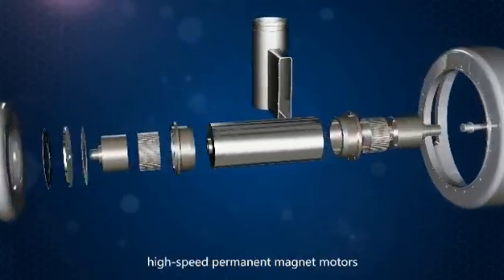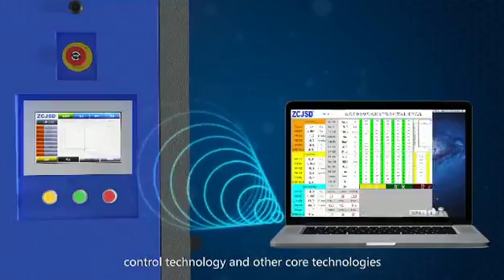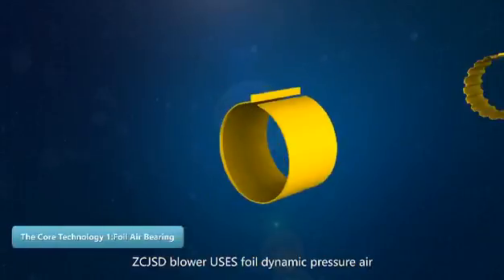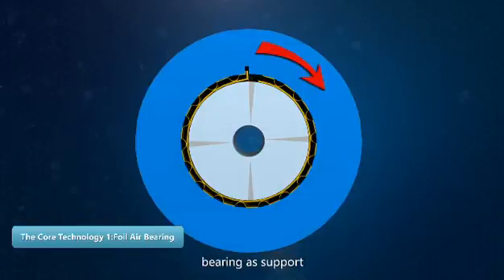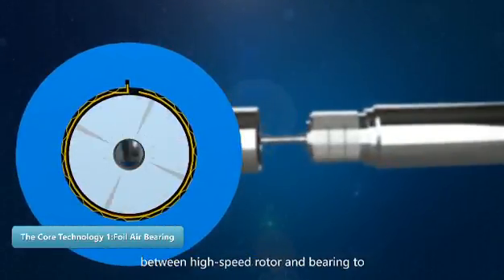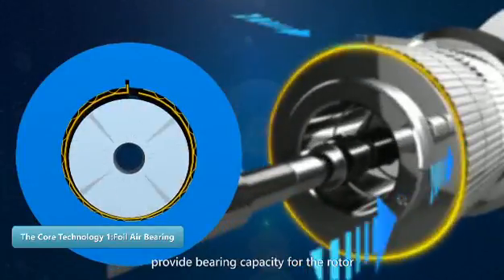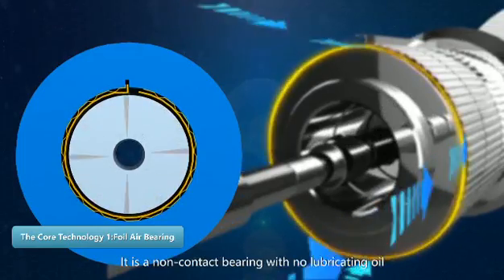Our blowers focus on foil dynamic pressure air bearings, high-speed permanent magnet motors, ternary flow impellers, and automatic control technology as core technologies. The ZCJSD blower uses foil dynamic pressure air bearing as support and uses a wedge compressed gas film between the high-speed rotor and bearing to provide bearing capacity for the rotor.